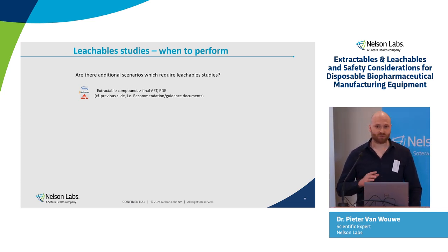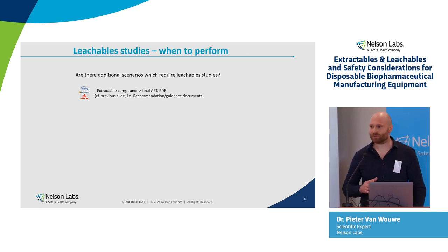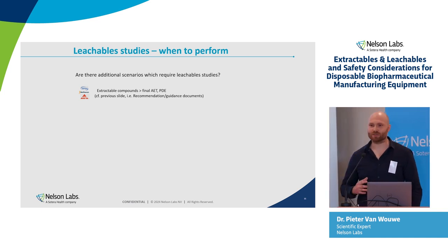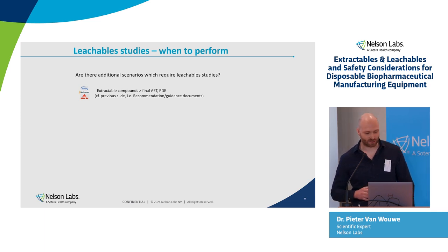And sometimes for some aspects, the authorities could have some more stringent requirements than what is actually written in those recommendation documents. So what we try to do as best as possible is collect direct and indirect feedback from our customers, and based on that also give the right recommendations back to our customers in which cases they actually need to do the leachable study.